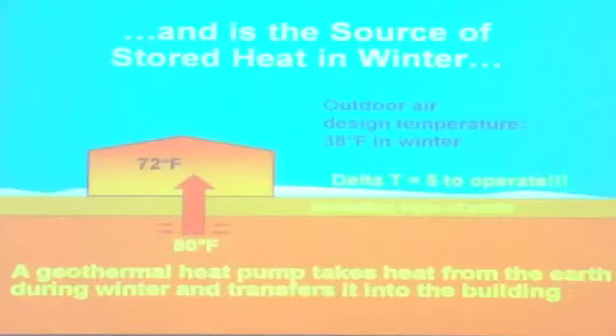Is there any damage to the soil from heating or cooling it, from changing the temperature in the soil? It depends on what your soils are and what your heat profile looks like. If you've got limitations because of the soil type, then it'll change the design of the heat exchanger. But you can get it where you swing the earth only a couple degrees. But Greg, it doesn't make anything toxic, right? No. Right, it's strictly heat. All it does is warm the soil, sands, clays, rocks, whatever it is.